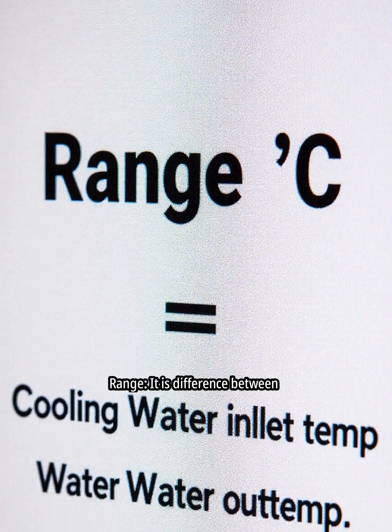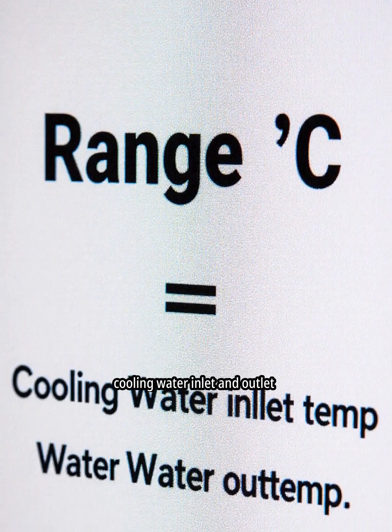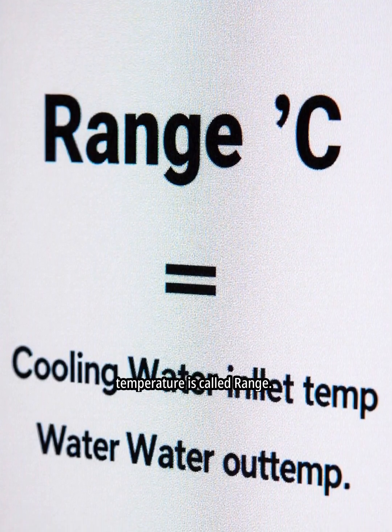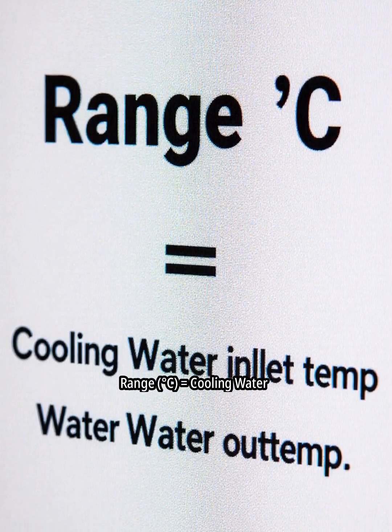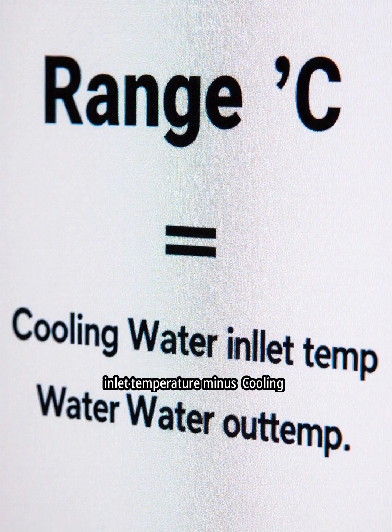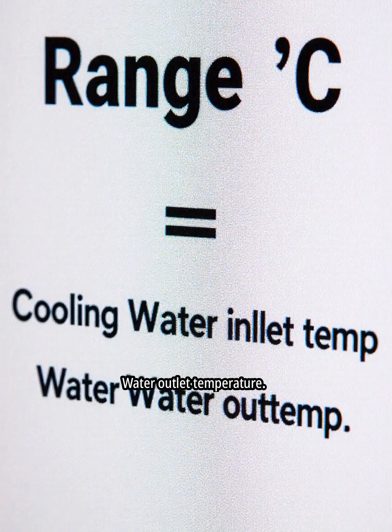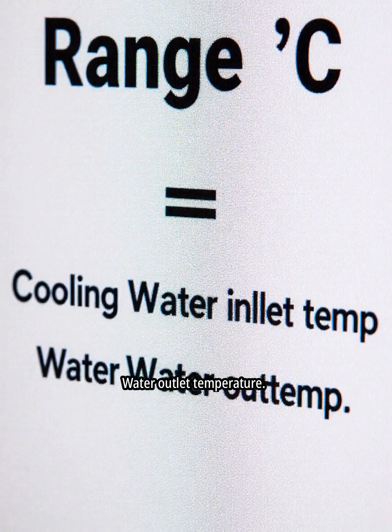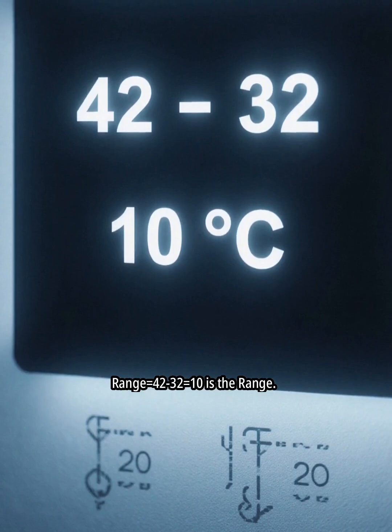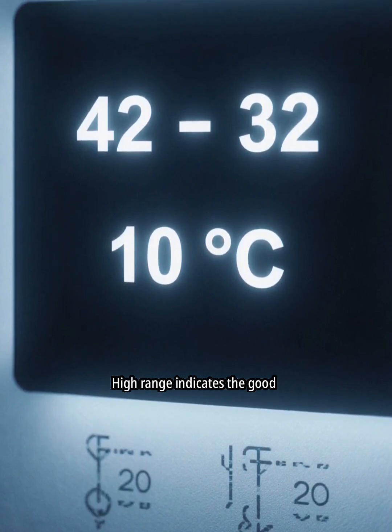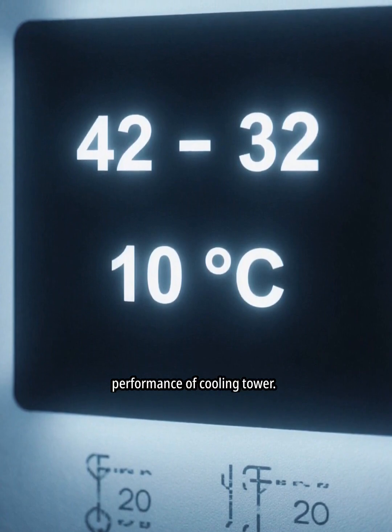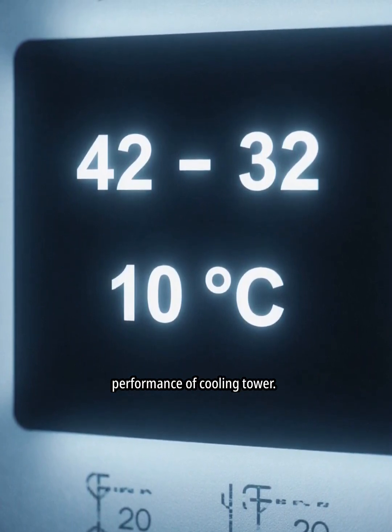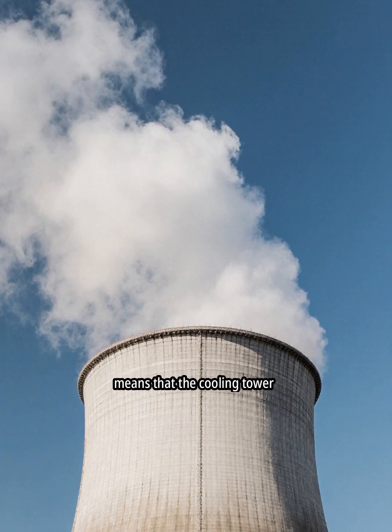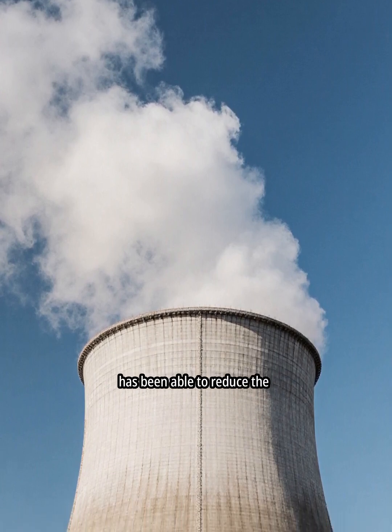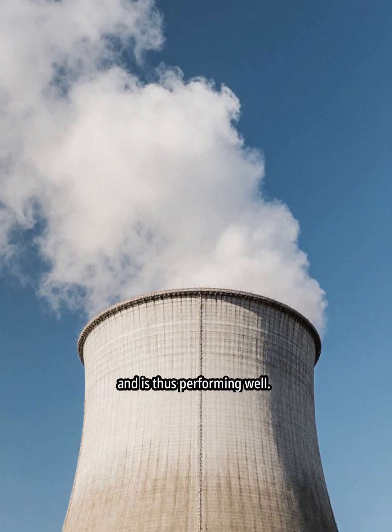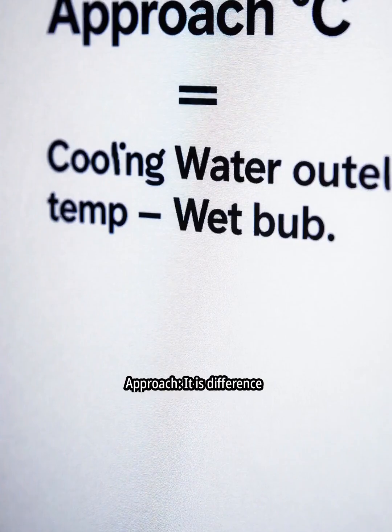Range. The difference between cooling water inlet and outlet temperature is called range. Range in degrees Celsius equals cooling water inlet temperature minus cooling water outlet temperature. Range equals 42 minus 32 equals 10. High range indicates good performance of the cooling tower. A high cooling tower range means that the cooling tower has been able to reduce the water temperature effectively and is thus performing well.